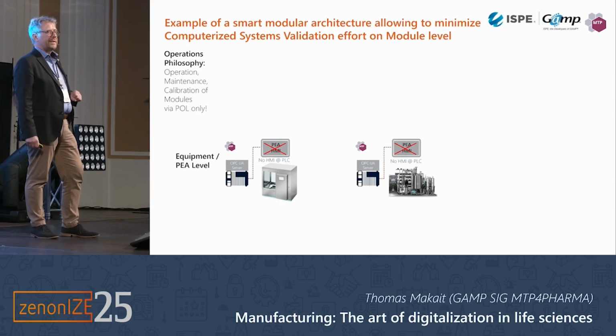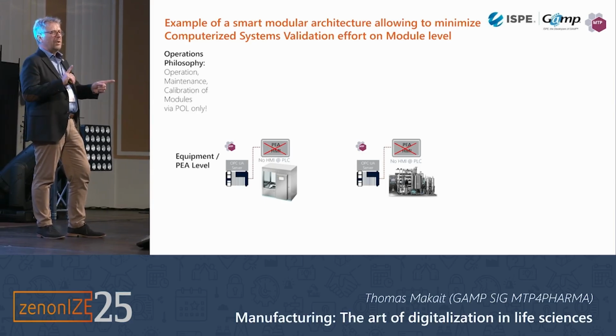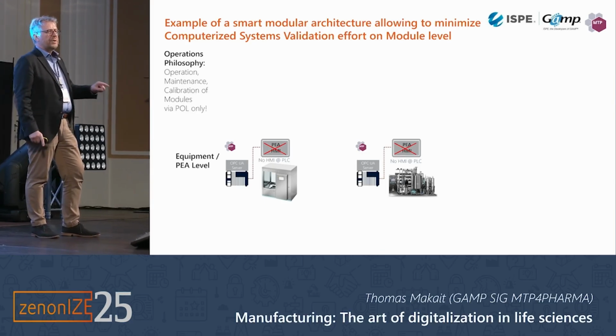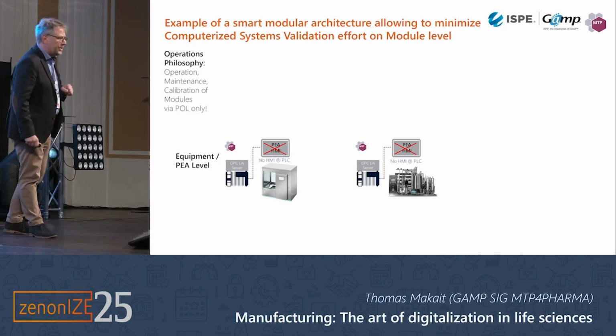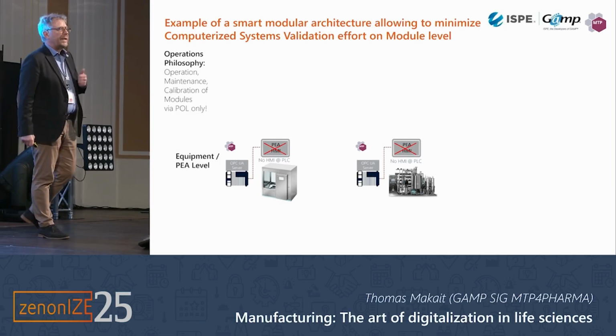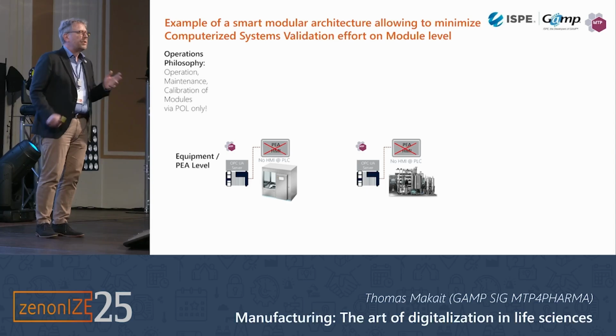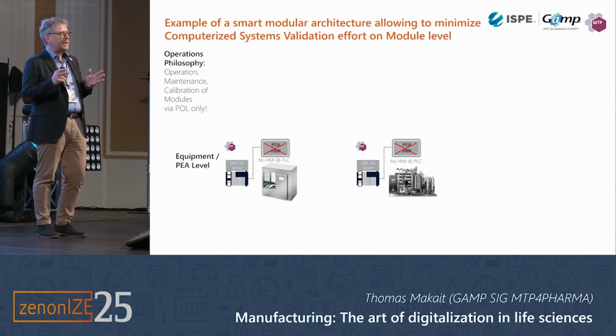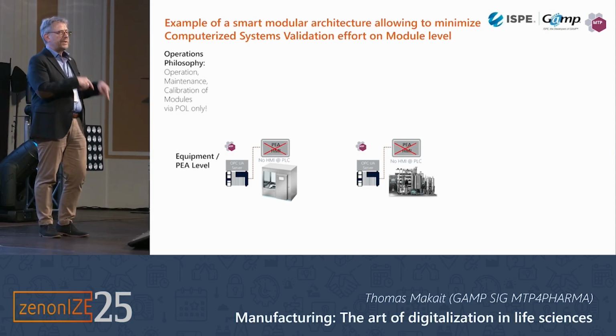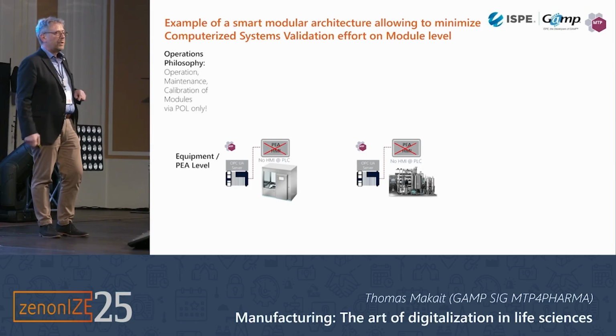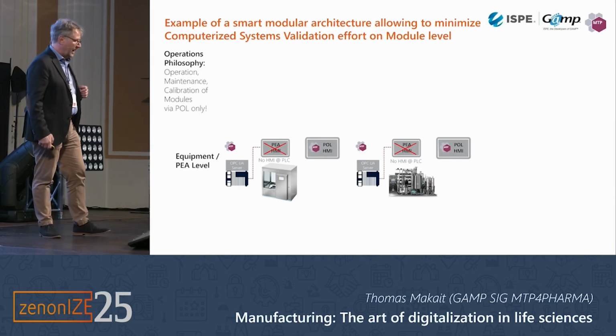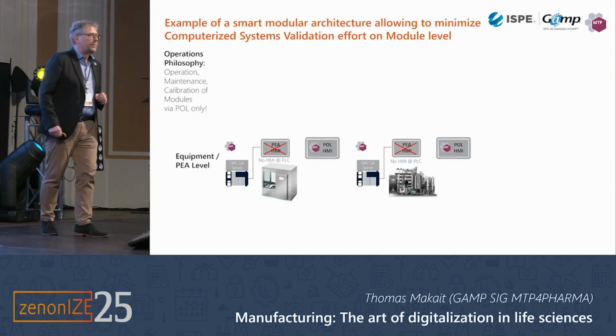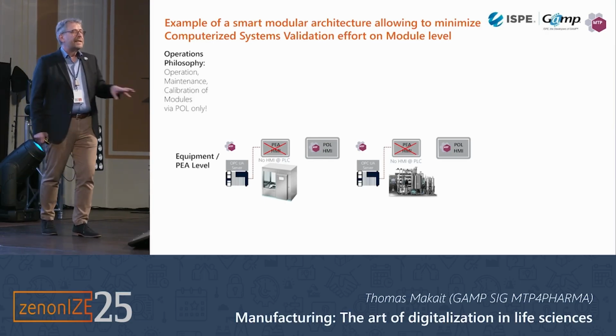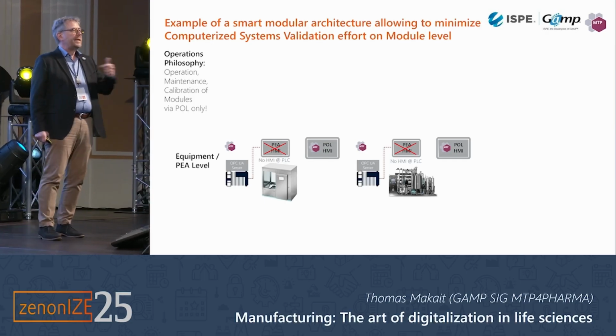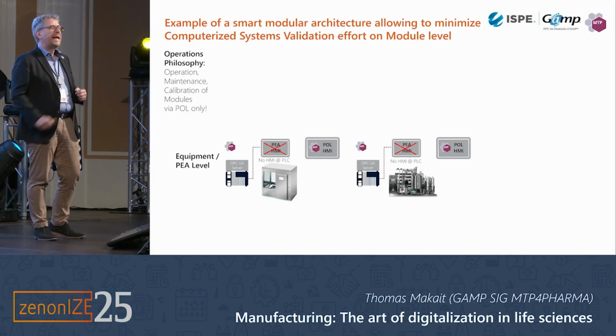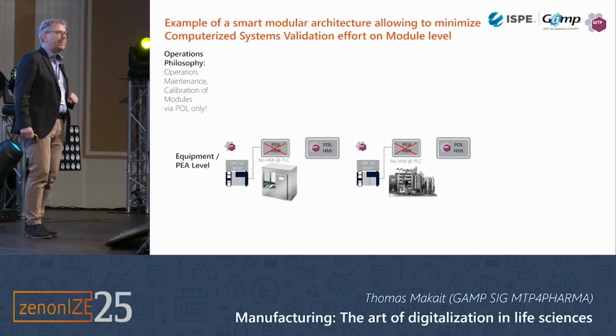Why is this? There's a lot of argument going on, because once you have an HMI at the PLC, you have audit trail, user management, access management, all these data integrity topics you have to solve twice — on the equipment level and later at the POL level. You ask the equipment supplier to design the HMI for operation, maintenance, calibration, and put it in the XML file, in the MTP.